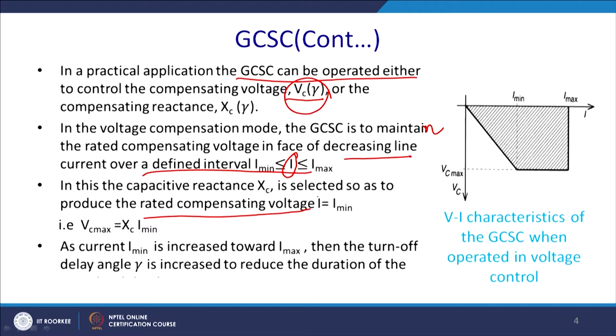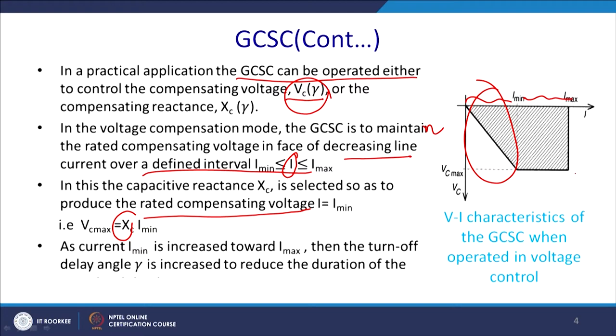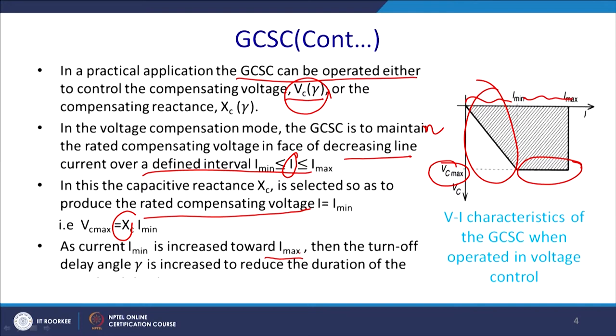We have to maintain the desired voltage level by controlling I within its range. In the capacitive reactance mode, X_c is selected so as to produce the rated compensated voltage, so that V_c_max equals X_c times I_min. This is the V_c_max at I_min, and this is I_max. You can control in this region — this is constant impedance mode — analogous to the constant torque and constant power regions of a DC motor.